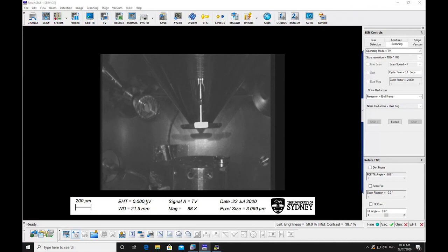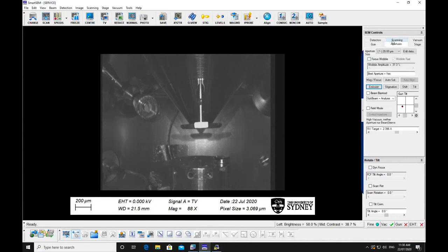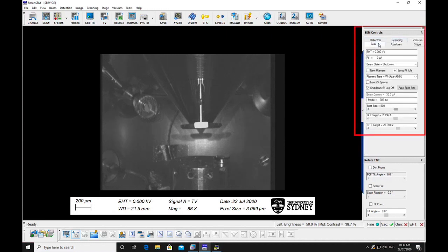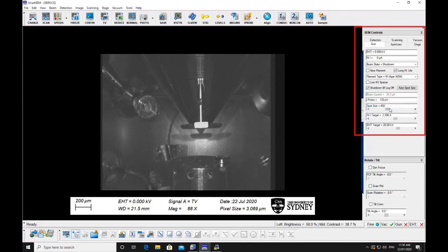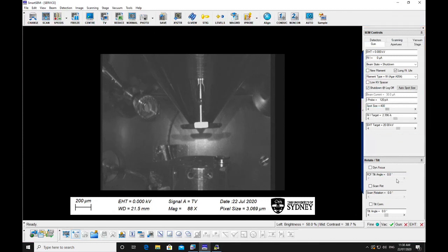Select the accelerating voltage and spot size appropriate for your intended imaging conditions. Smaller spot sizes around 350 to 400 will give you better resolution but less beam current. Larger spot sizes around 500 to 550 give lower resolution but more beam current.